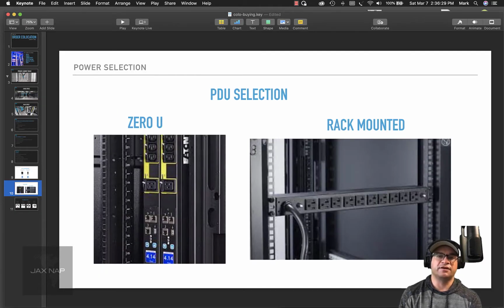Okay, after you selected the kind of power you need, whether it's 208 or 120, you're going to have to figure out exactly what you need for the PDU selection. You need to find out first if the data center is going to provide you with the PDU, and if so, are they going to provide you with a 0U PDU or a rack-mounted PDU? If you are obligated to actually provide the PDU, I would suggest a couple things. I suggest to use a 0U PDU because it doesn't take any rack space.